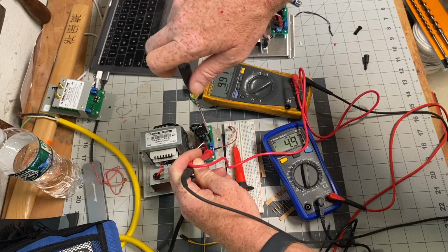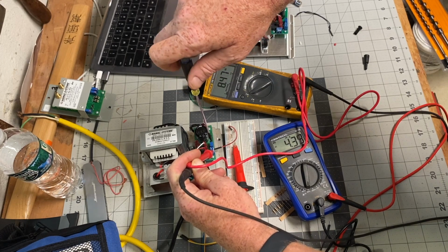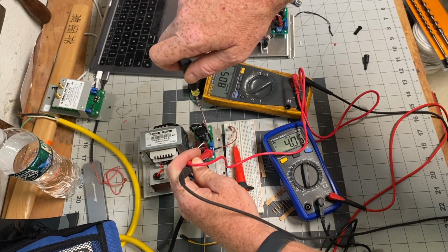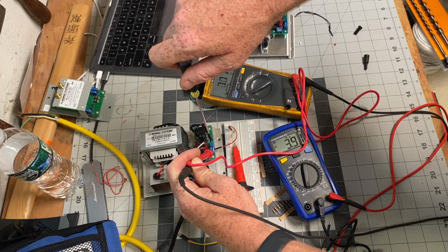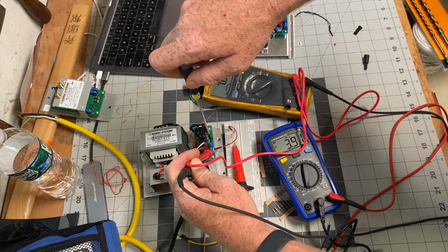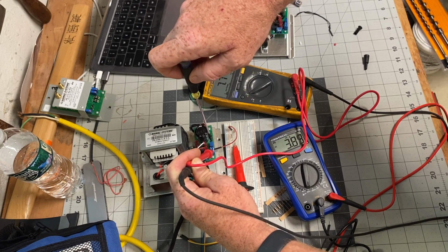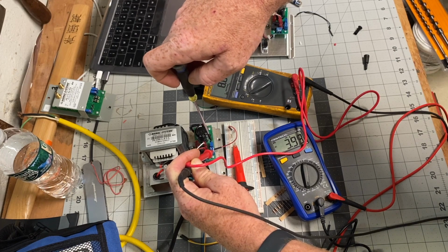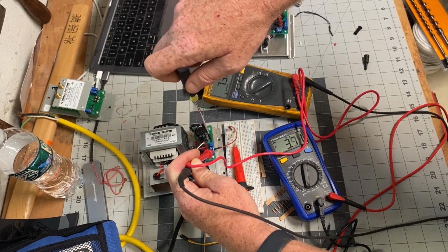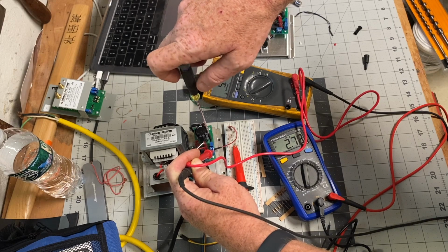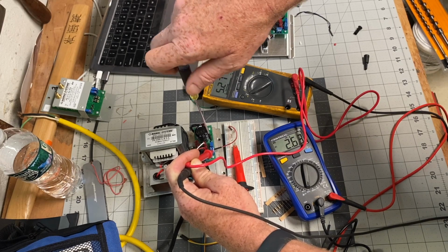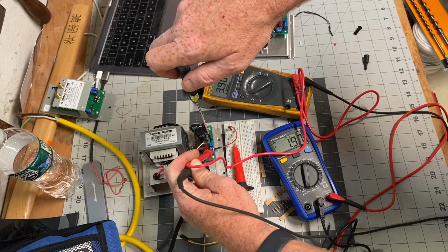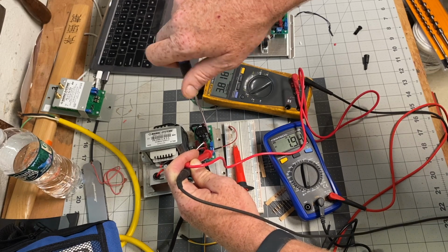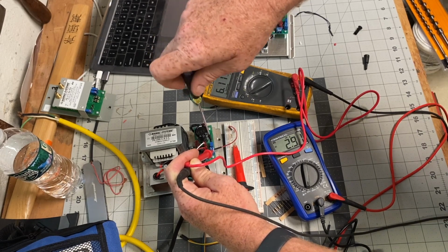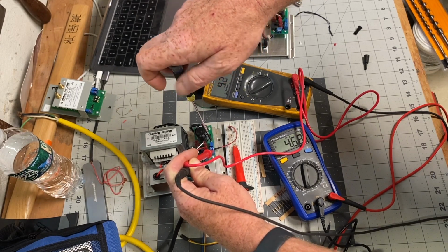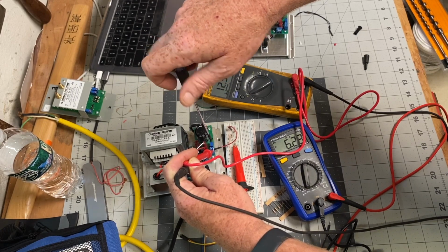The point where the BMS system, if it drops below 4 milliamps, it'll usually read a fault. That's right around 8 volts. Right? And this power supply will go down below 5. It is adjustable. Right? So we'll get back up to the 24 volts DC. I want to show you the other power supply.